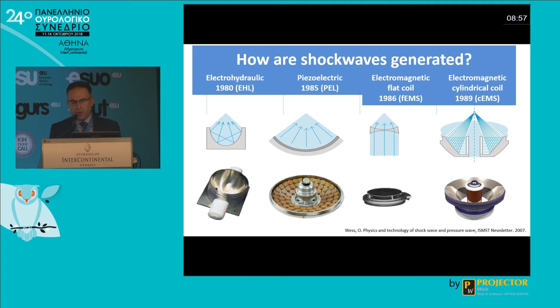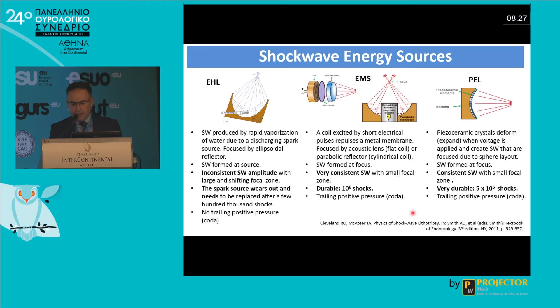Historically, the first shockwave machines were electrohydraulic back in the 1980s. Then came the piezoelectric and the electromagnetic. The main problem with electrohydraulic devices is that they produce inconsistent shock waves, and there is a slight shift in the focal zone. The spark source, which generates the shock wave, tends to wear out and needs to be replaced. The electromagnetic produce very consistent shock waves, and they are durable. And so are the piezoelectric, which actually are very durable. We can see that they can last up to 5 million shocks.